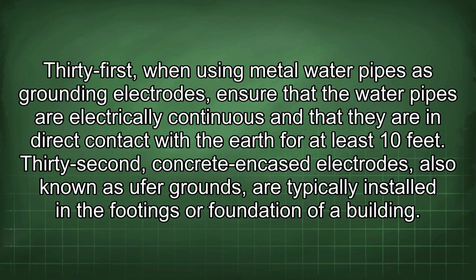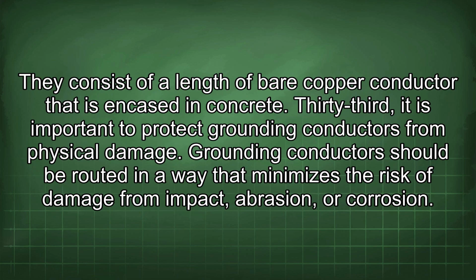32nd. Concrete encased electrodes, also known as UFER grounds, are typically installed in the footings or foundation of a building. They consist of a length of bare copper conductor that is encased in concrete. 33rd. It is important to protect grounding conductors from physical damage. Grounding conductors should be routed in a way that minimizes the risk of damage from impact, abrasion, or corrosion.